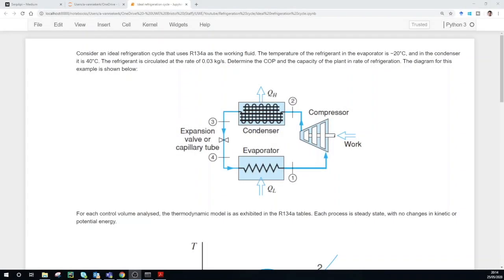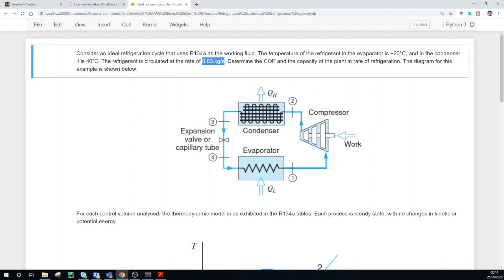For this problem we are considering a refrigeration cycle that uses R134a as the working fluid. The temperature of the refrigerant in the evaporator is minus 20 degrees Celsius and in the condenser it is 40 degrees Celsius. The refrigerant is circulated at a rate of 0.03 kilograms per second. We need to determine the coefficient of performance, the capacity of the plant, and the rate of refrigeration. You can see here is a diagram where the refrigerant leaves the evaporator at minus 20 degrees Celsius, the compressor does some work on it, it gets compressed to a higher pressure at point 2, then enters the condenser where heat is extracted, and is throttled over an expansion valve back to a very low pressure.